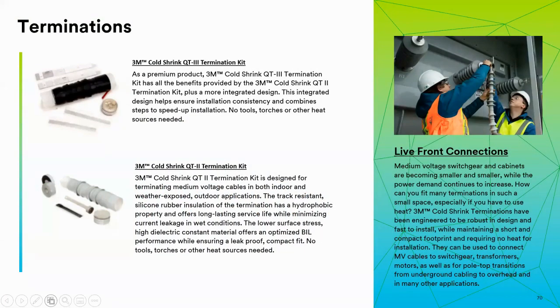3M terminations are very reliable thanks to an integrated high K stress control, which in the QT3, you see at the top of the screen there, does not have to be installed as a separate step. It's basically built into the termination itself. So these are very easy and fast to install. Uses high performance silicone material. It has a very compact design and a short termination. Even our outdoor terminations are short, which I'll show you here in just a second. No tools are required, like heat shrink. So it's definitely a go-to for quick installations. That's where it got the name QT. It stands for quick term.